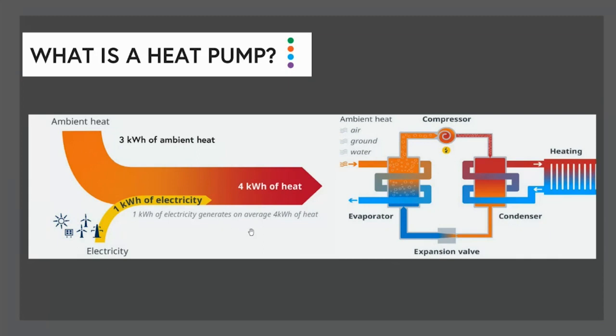So given that, how does it do this? Well, we move over to the right-hand side now, and have a look at the components of a heat pump. There are 4 major components: the evaporator, the compressor, the condenser, and the expansion valve. So let's start with the evaporator. The evaporator is the part outside. It is a coil or a heat exchanger sitting out in the atmosphere, for an air to water heat pump, and it's full of refrigerant.